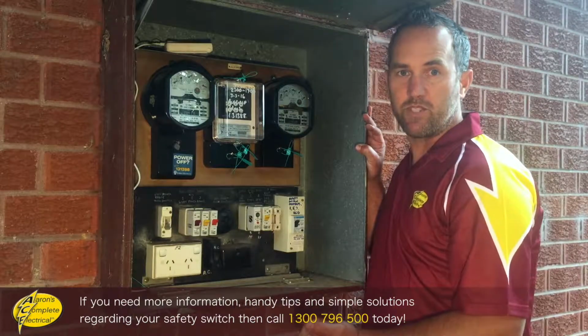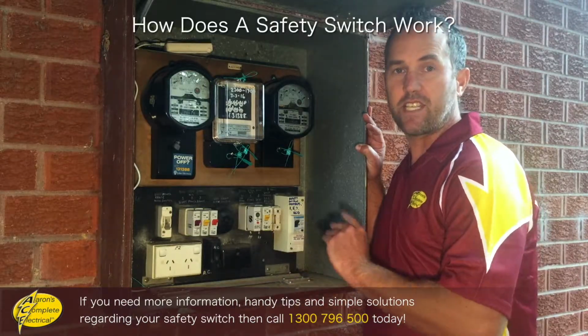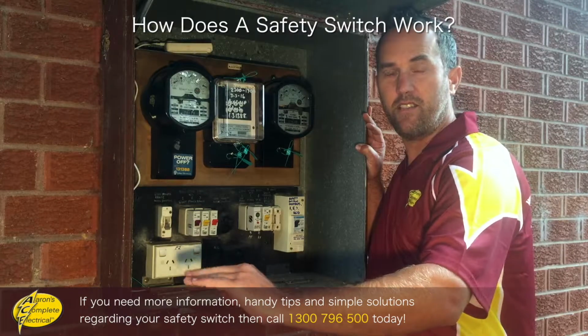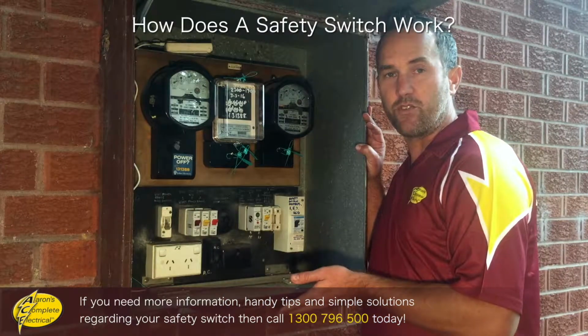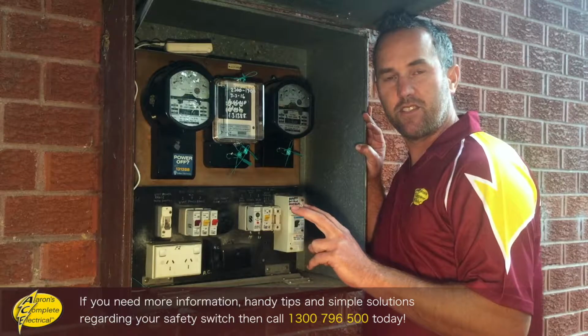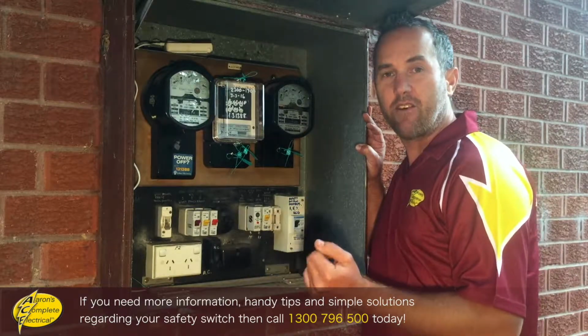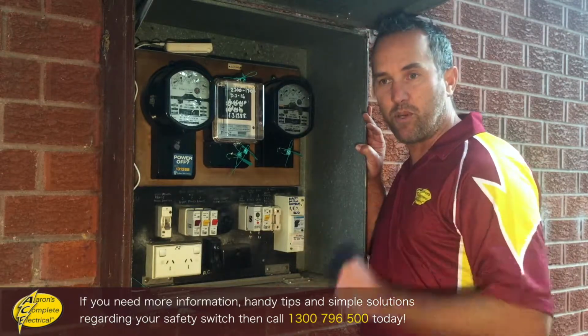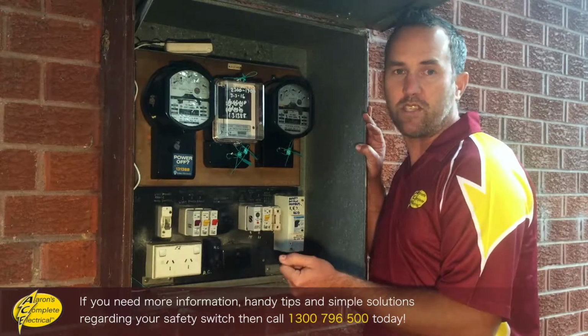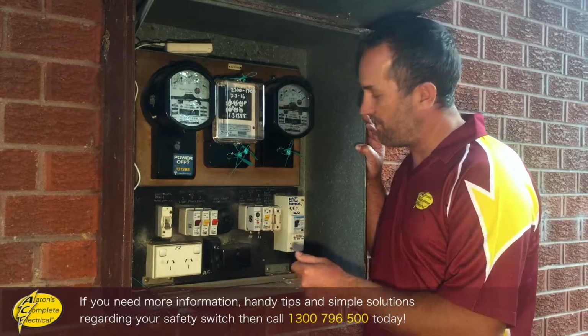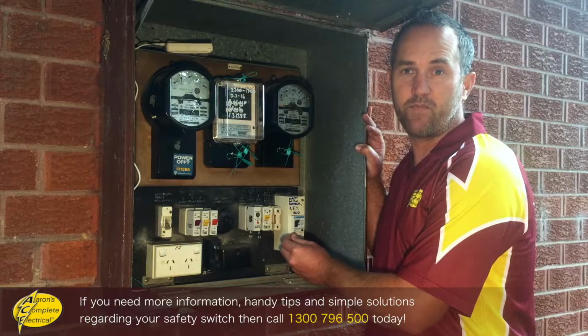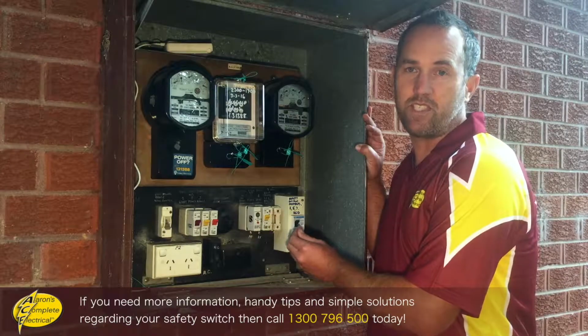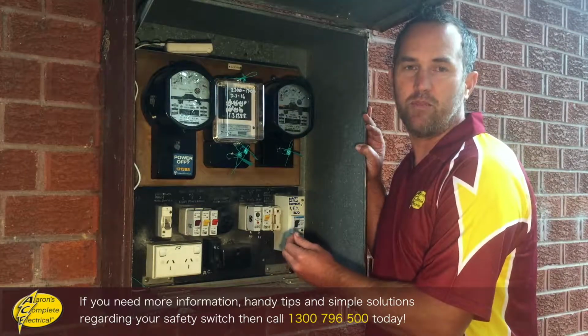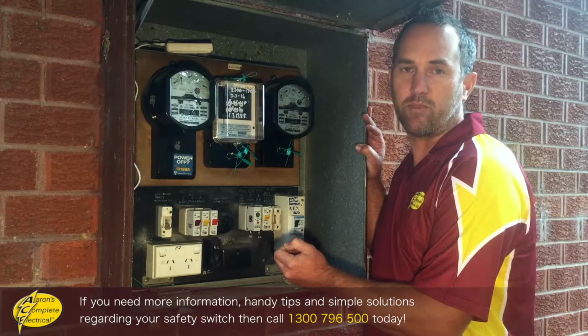The way a safety switch works is it measures the current going out on the active line and the current coming back in on the neutral line. And if there's any difference, then that means the current is leaking somewhere, either through a person down to earth or through a faulty appliance or faulty wiring down to earth, and the safety switch will trip. When the safety switch trips, it's doing its job. It's telling you there's a problem, and you've got to find what that problem is.